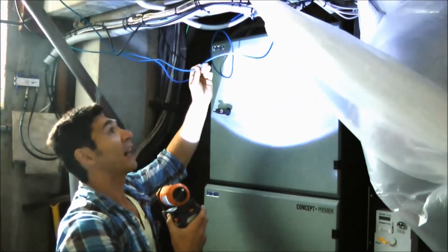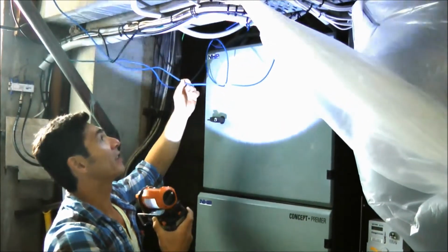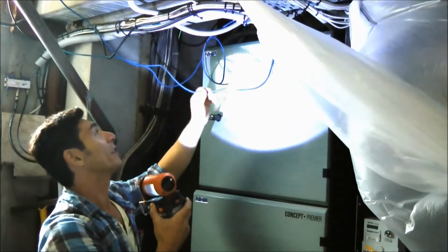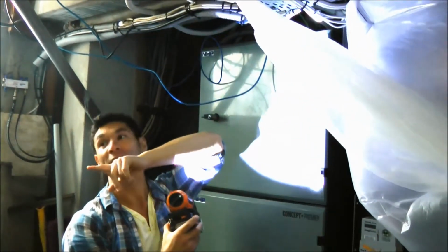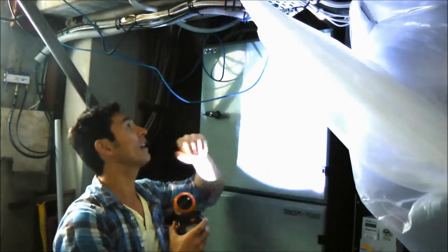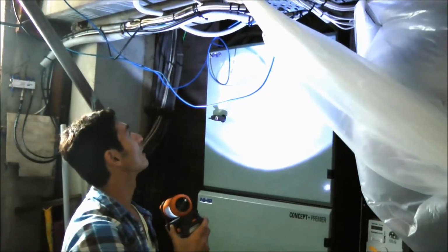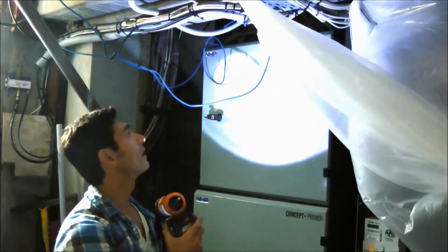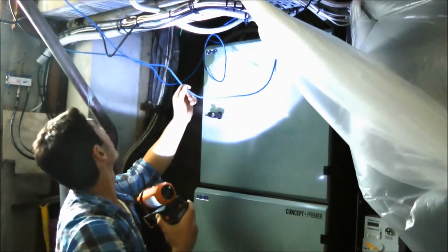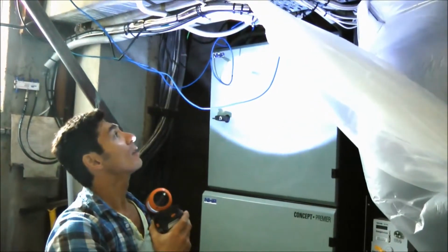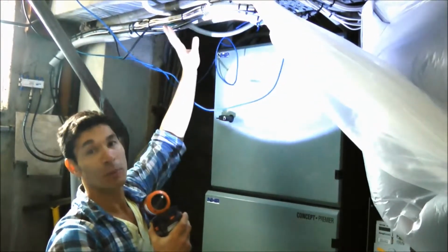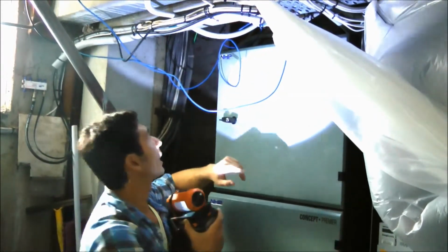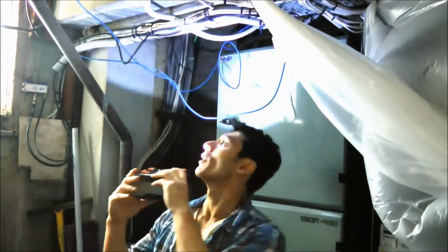These blue cables are telecommunication services, and you can see people have just run these cables direct to the mainframe over here just to my side there, and it's illegal. So we're going to fix all this up and have proper telecommunication services run inside conduit so it's fully protected and safe. We're going to run them along here, along the roof.